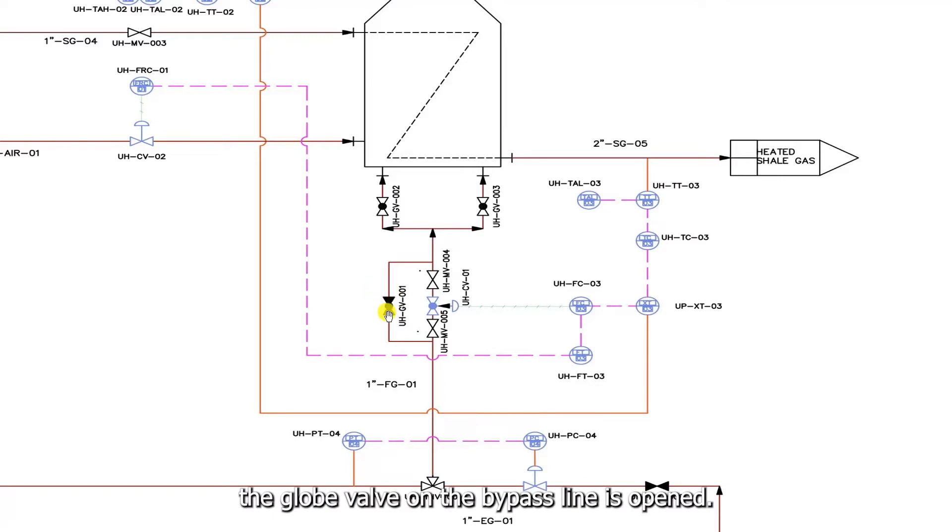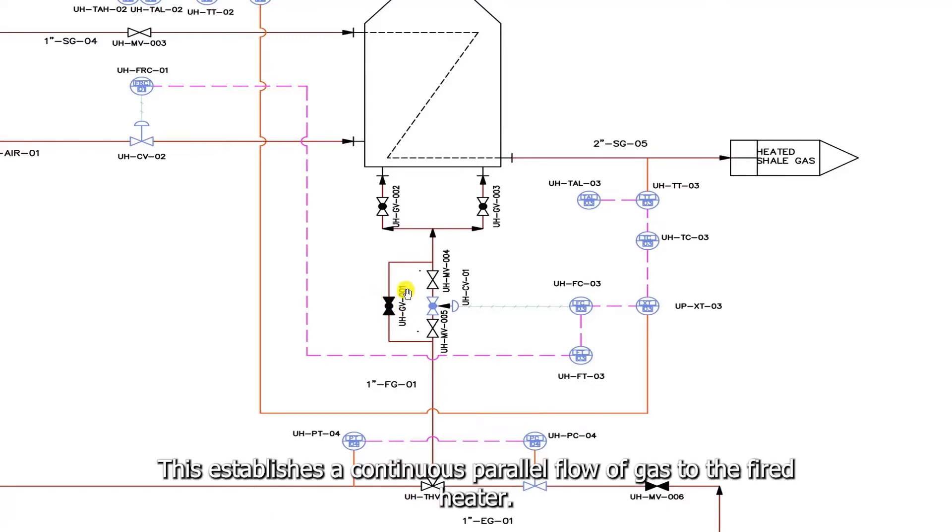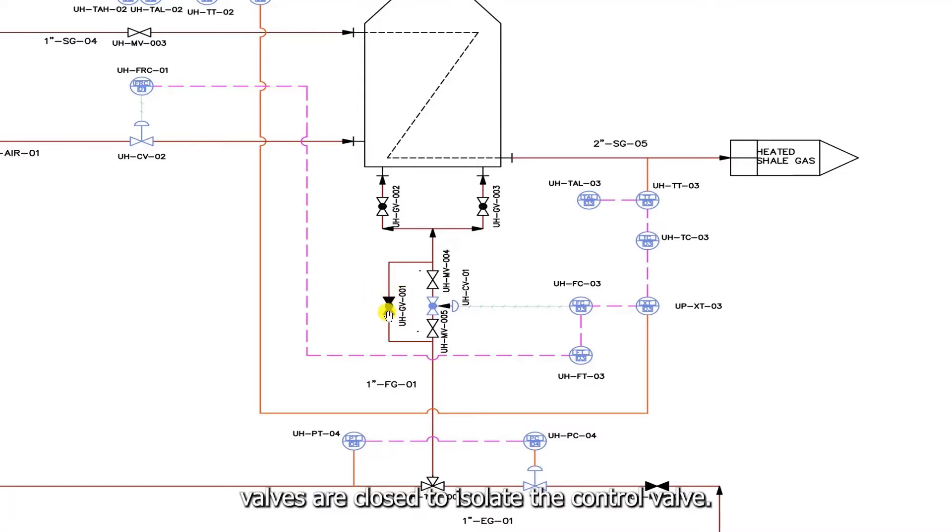First, the globe valve on the bypass line is opened. This establishes a continuous parallel flow of gas to the fired heater. Next, the two manual gate valves are closed to isolate the control valve. This action interrupts the flow of gas through the main line. This has no effect on the process continuity, as the bypass line is open, and gas is flowing through it.